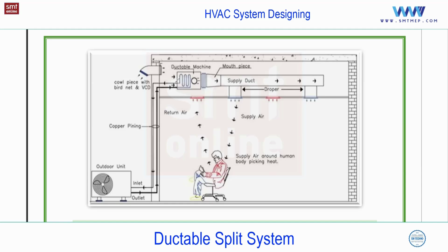Just as a thumb rule, what I explained is 10 to 30%, but we need to do the calculation for this. According to that calculation only, we will provide the fresh air. And we have a separate calculation for this at the time of the load calculation. Next, we have some more points to discuss.